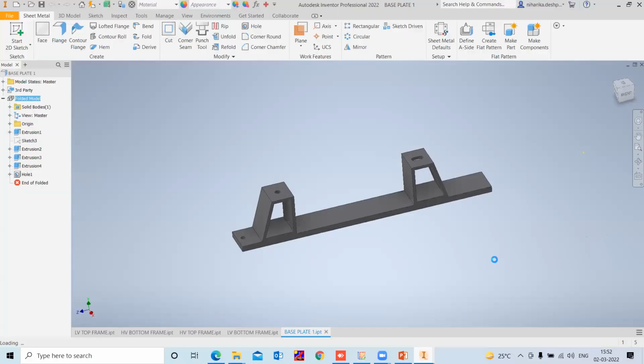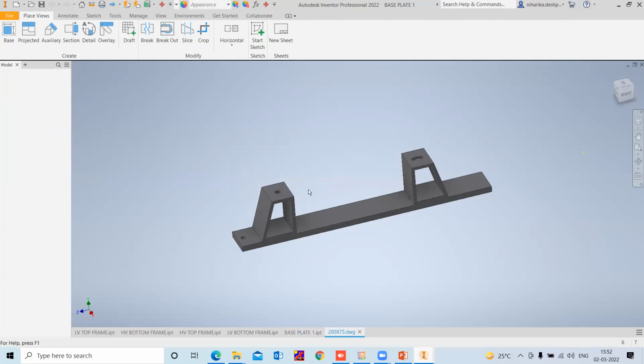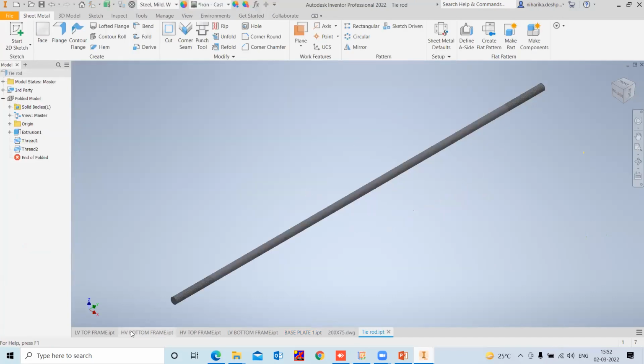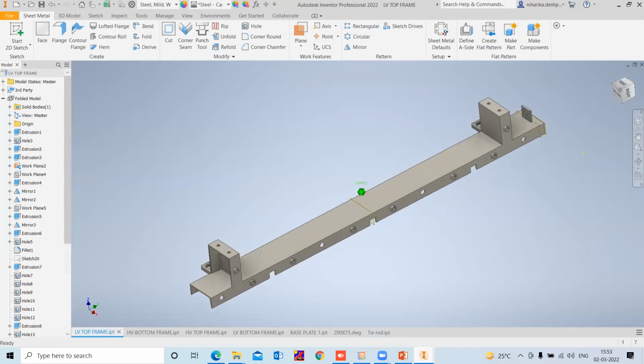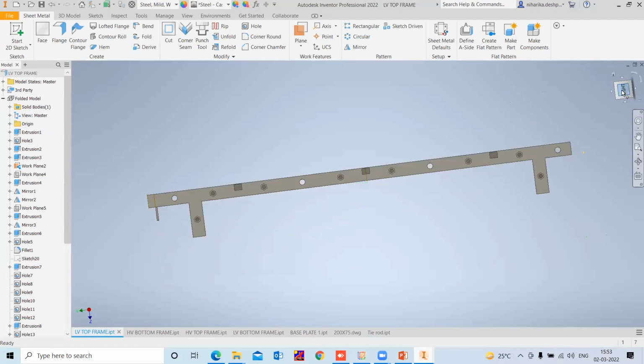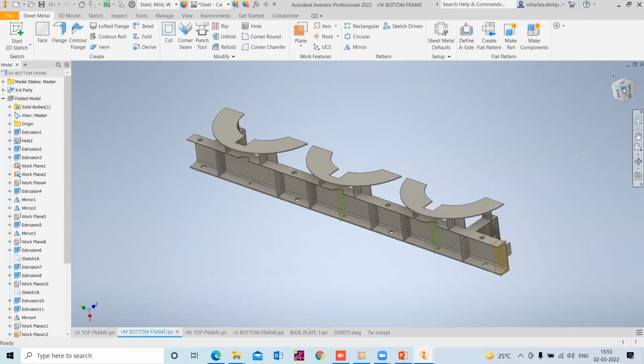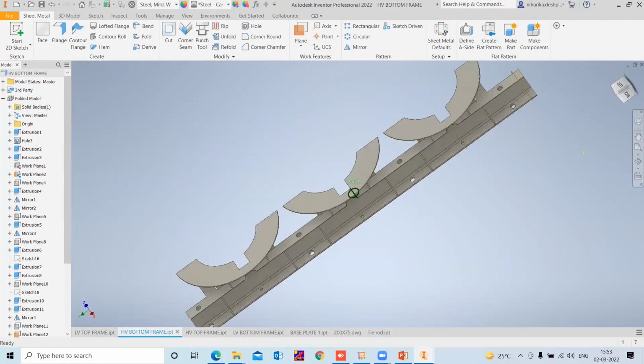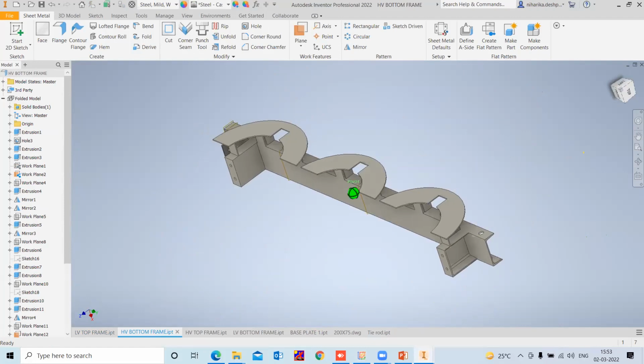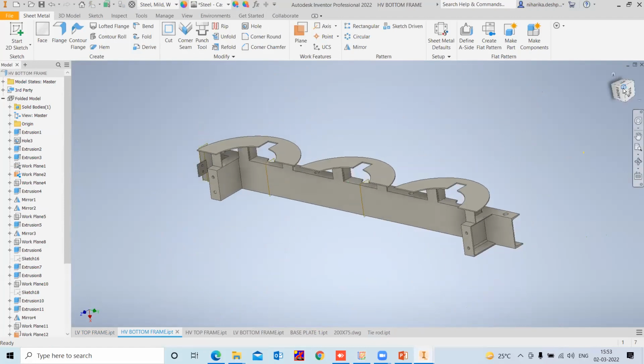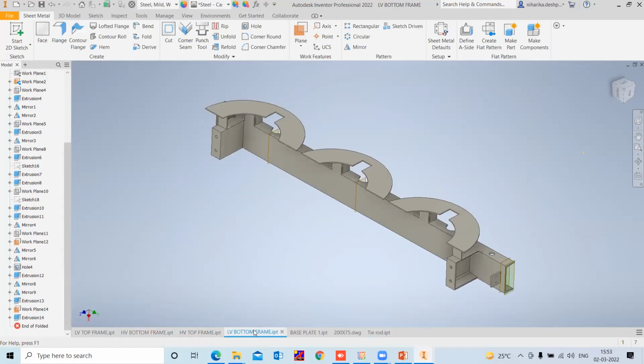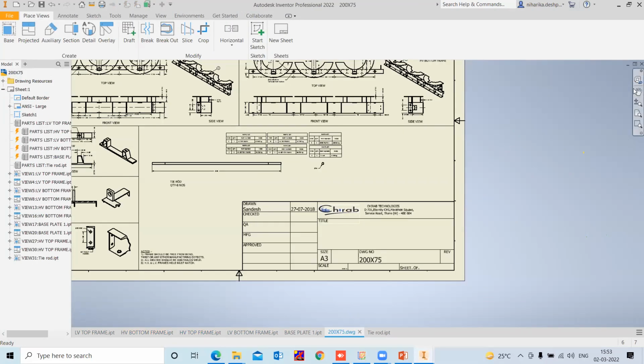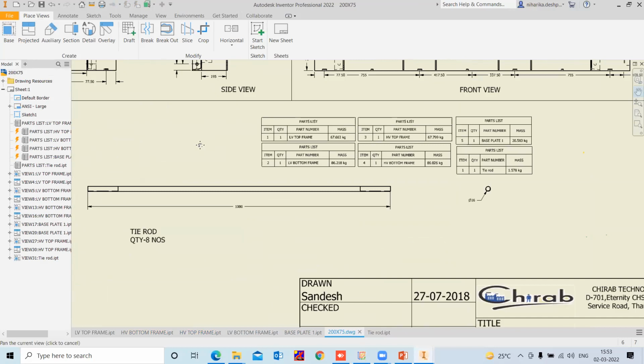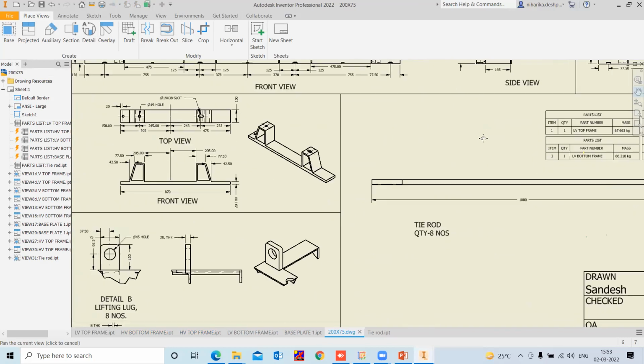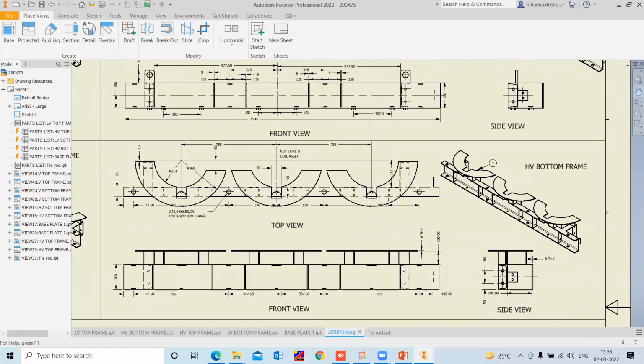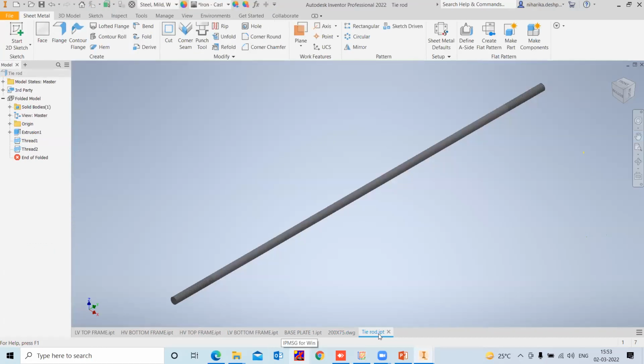So see, drawings are generating, the message for 2D diagram. Now this is the frame for 10 MVA drawing. You can see the support plate is provided, and for OLTC leads there are the cutouts. Then HV frame, then LV bottom frame, then base plate, and this is the drawing in 2D, including the weight details and each and every cutout. Thereafter, the tie rod drawing is available here.